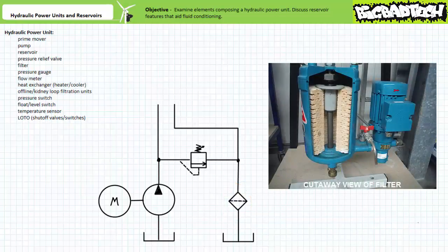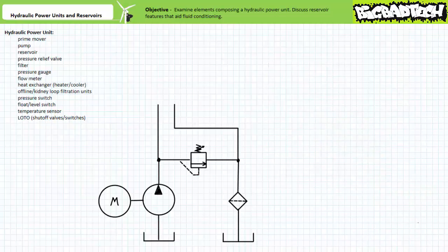A filter is a porous element, similar to a net, through which small holes allow the passage of particles smaller than the holes, however exclude and entrap those particles larger than the holes. Long story short, dirty liquid with suspended particles comes in, and cleaner liquid with fewer suspended particles comes out. Any fluid routed through the system must go through the return filter at low pressure prior to being emptied into the reservoir. The return filter's job is to remove contaminants from the larger system.